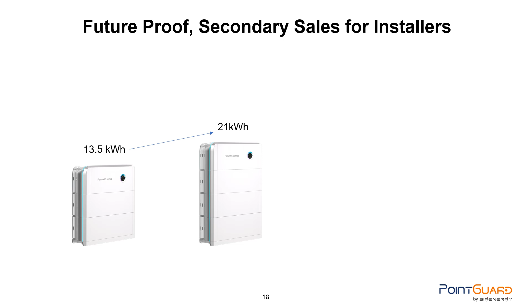We have been able to future-proof our system, creating the opportunity for secondary sales for installers. There are way too many systems out there that are not backwards compatible, and manufacturers like to release a new version of their system every 2 years or so. With PointGuard, you are able to add to your system at any time during its life cycle. You can add a battery to a 13.5 kilowatt hour system and make it a 21 kilowatt hour system. 3 years later, you might come back and add our PointGuard V2X module, which is our bidirectional EV charger. This provides the opportunity for you to be relevant to the homeowner throughout the life cycle of the system and to keep upselling them and making money throughout that time.